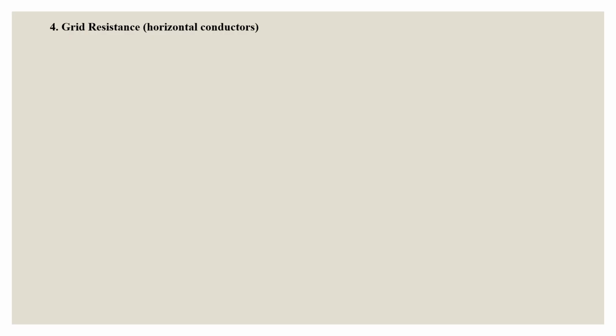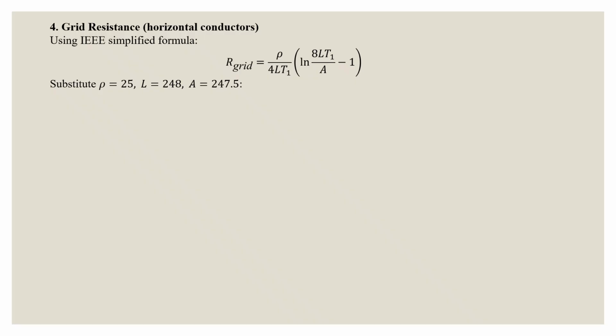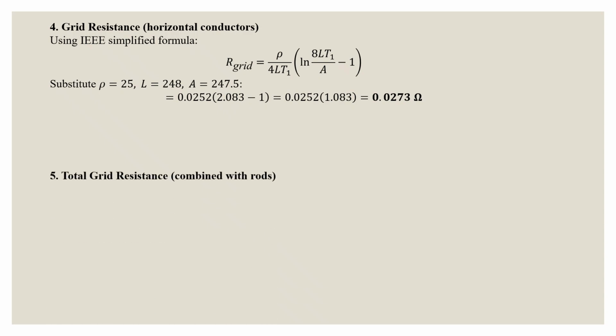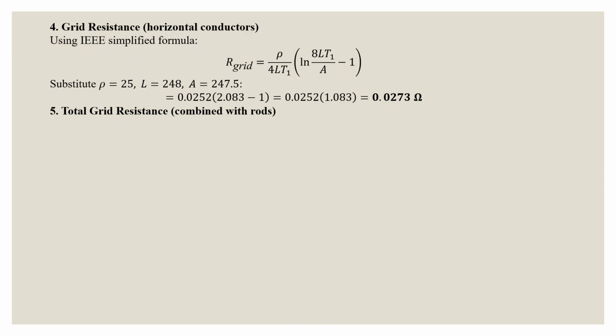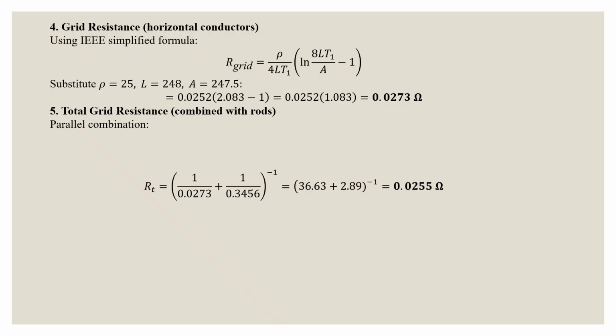Next, we will calculate grid resistance for horizontal conductors using the IEEE simplified formula, which is shown, and by substituting the given data into the formula, we have the resistance value as 0.0273. Then we have to calculate total grid resistance combined with rods, means grid resistance and rod resistance combined all together. For parallel combination, we have this formula. And by substituting the given data, the resistance is 0.0255 ohms.